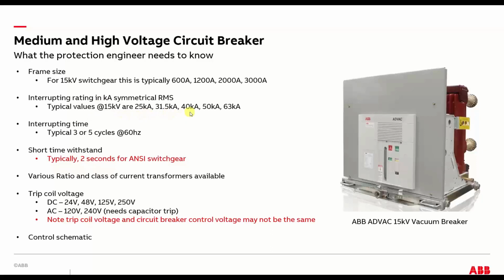Now they're all done in KA, just like low voltage. It used to be a different system, but it's changed over the years and got a little bit simpler. Typically, they interrupt in either 3 or 5 cycle. Historically, 5 cycle was pretty common, but now I think the 3 cycle breaker is a little bit more common and pretty readily available. And this is important because this determines how fast you have to add this time onto the time it takes for the relay to pick up, and we'll kind of get into that.